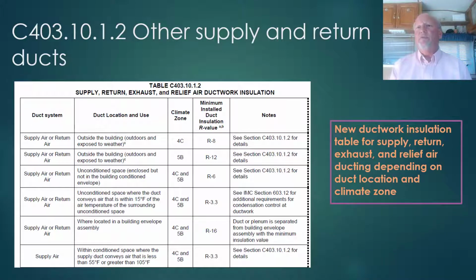We also have a new table for supply, return, exhaust, and relief air ductwork, and it's a similar format. Based on the service of the duct system, the duct location, and the climate zone, you can easily identify the minimum insulation value required. Again, it depends on where the ductwork is located, whether it's outside the building, in an unconditioned space, part of the building envelope, or within the building envelope. But as long as you can identify that and the climate zone, you can determine the minimum insulation values.